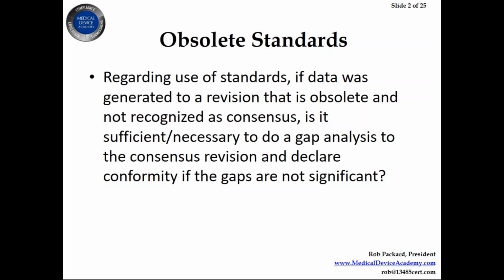Because it's very possible that you could have a standard that is in the process of being recognized by the FDA that was revised last year, and you could get halfway through your submission and then all the standards change and you have to redo all your testing, and that would be very painful and expensive. And I actually had that happen to a client where the sterilization standard was just one of the standards that changed on them. They actually had 6 different standards change all at the same time, all within a couple of weeks of each other, and it was just before we were about to submit.